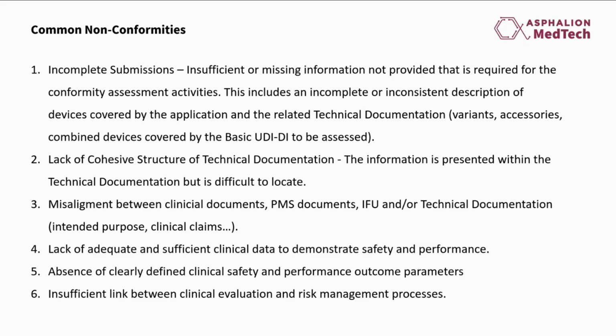Also, a lack of cohesive structure of the technical documentation. Again, these dossiers can be really long, so the clearer the structure you present for this documentation, the easier it will be to identify all the required evidence. Also, misalignment between documents. Remember that there could be a really close relationship between different documents in the technical documentation. So whenever you have to do a cross-reference, please make sure that you correctly identify the document that you want to cross-reference. Also, this is a critical deficiency: a lack of adequate and sufficient clinical data to demonstrate safety and performance.